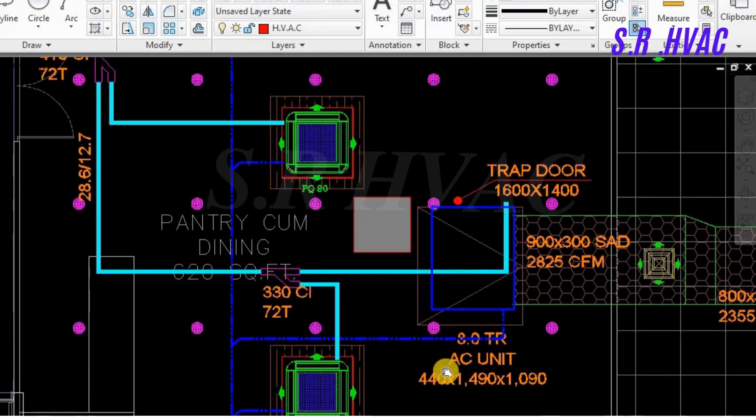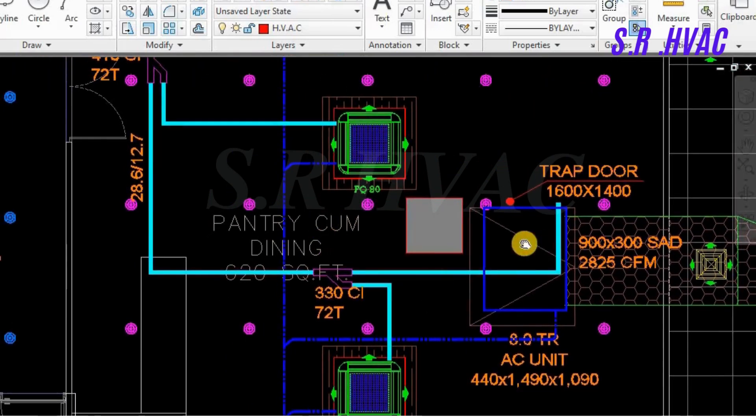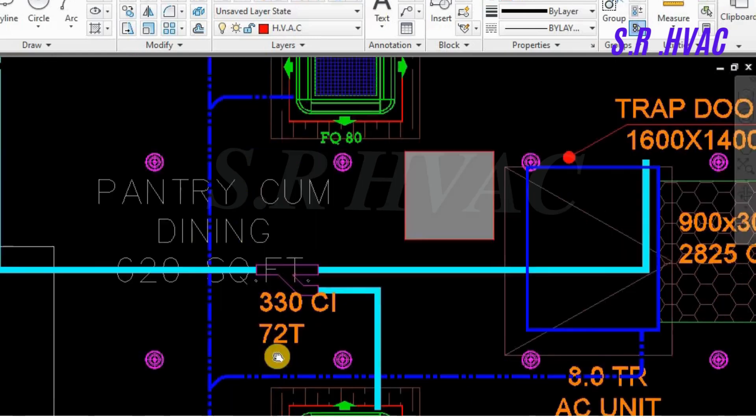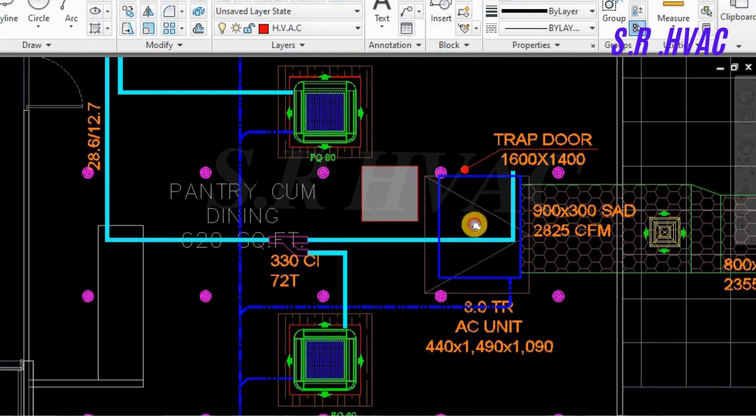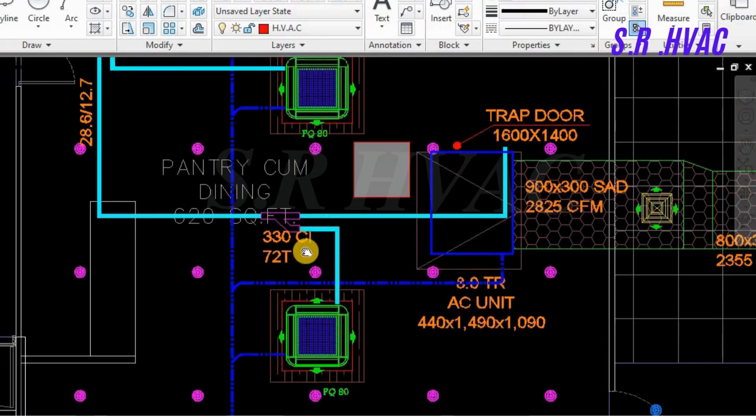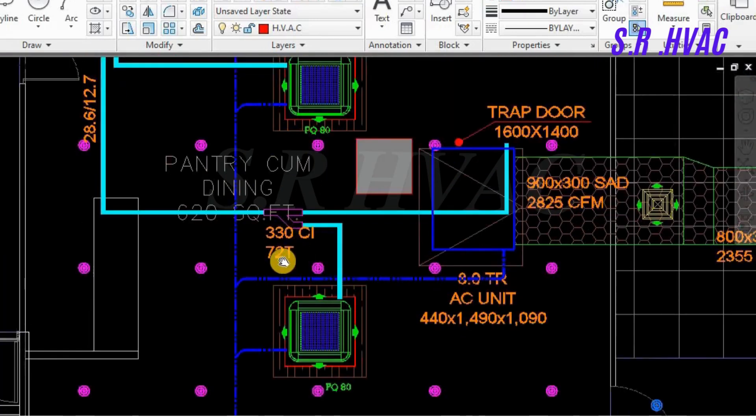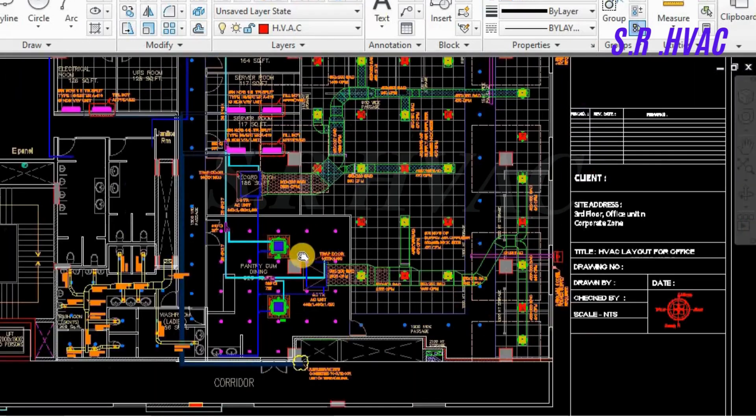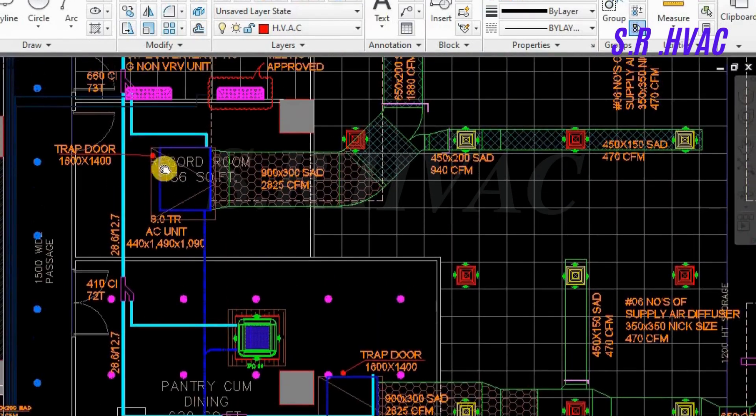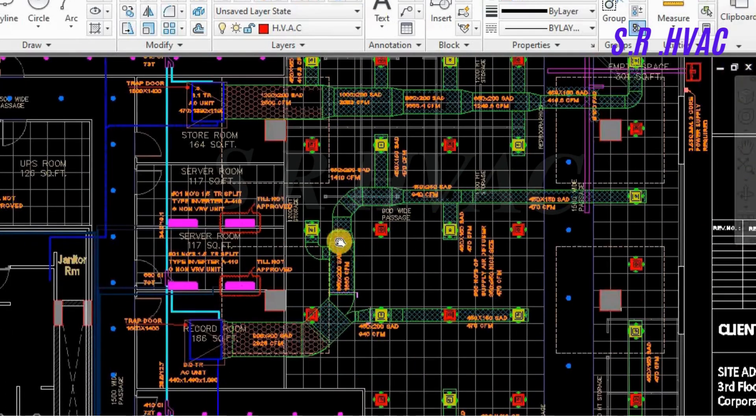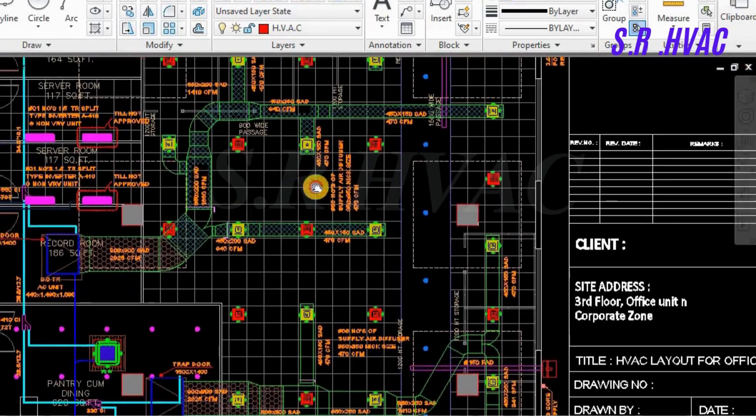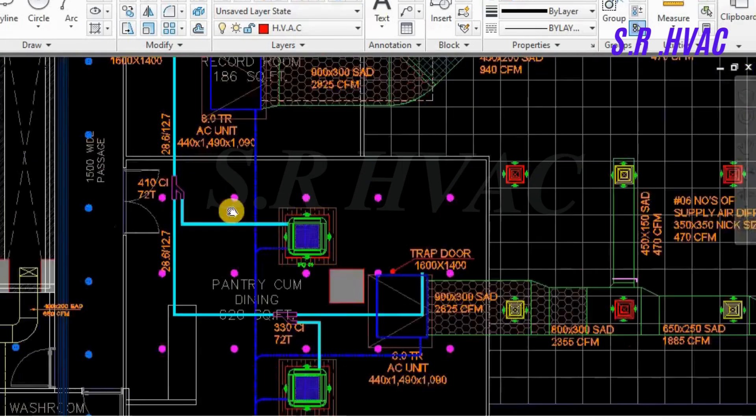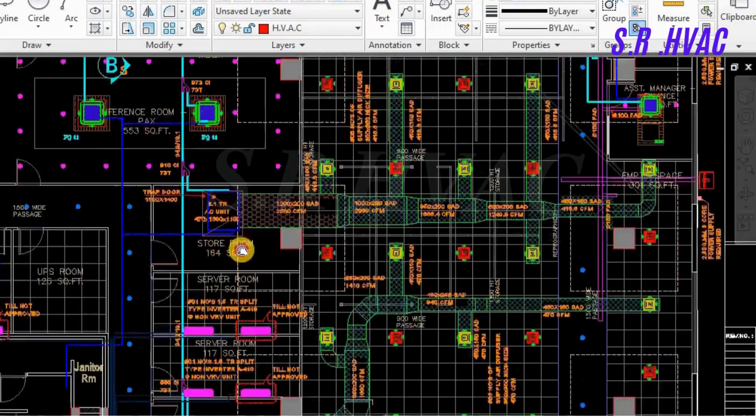FQ80 means 2.6. This is the 8TR ductable unit. This is also connected with the help of copper piping. You can see the refnet size is 72. It is 8, means it will be 250 plus 80, it is 330. So the refnet size is 72. And we have to check on our own whether there is anything missing dimension or any mistake. So we have to point out to the MEP consultant and our architect so that they can modify and approve it. So this is our VRV system.